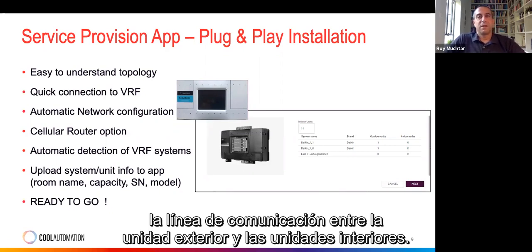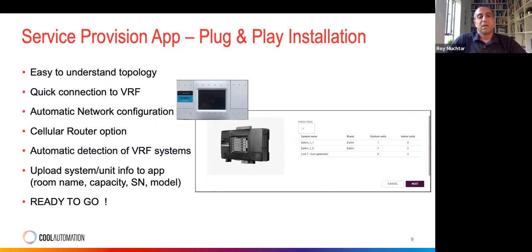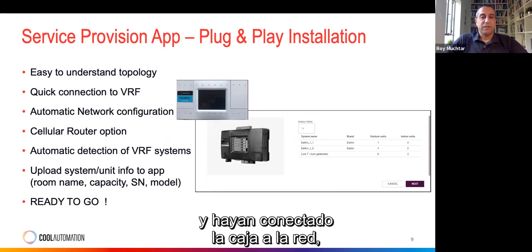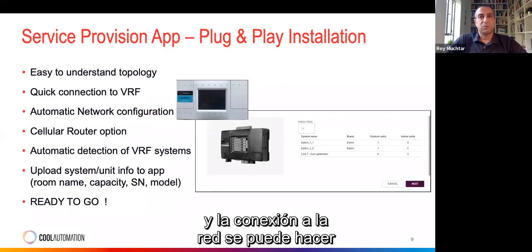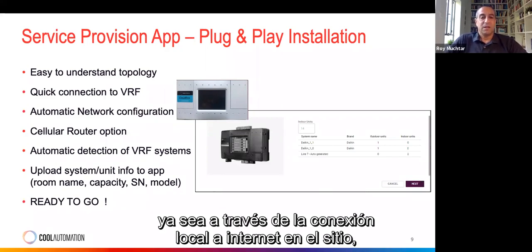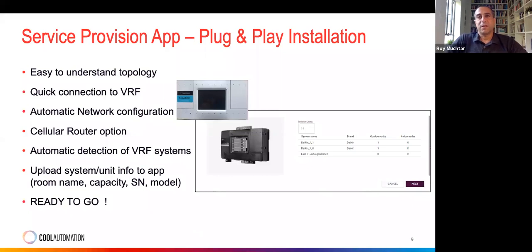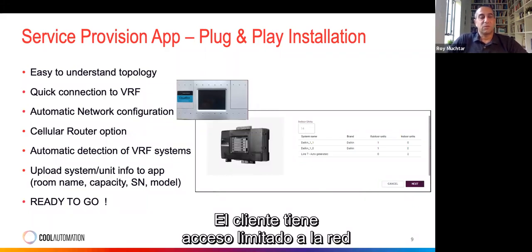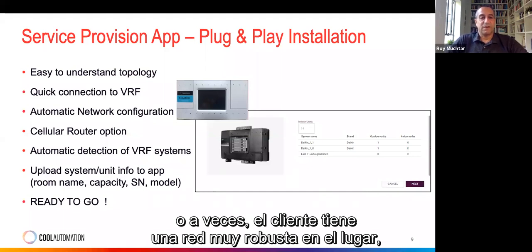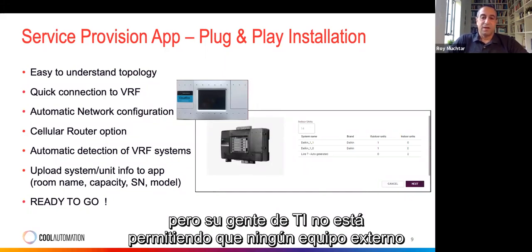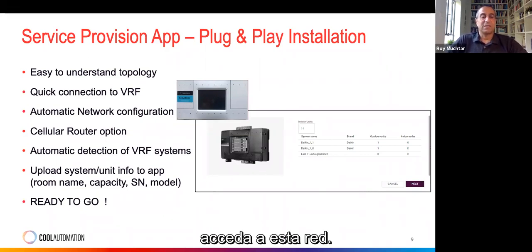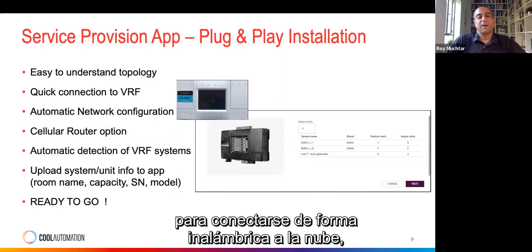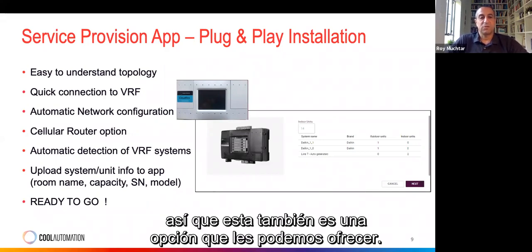The communication line between the outdoor unit and the indoor units, once connected, can be linked to the network either via a local Ethernet connection on site, or in places where the customer has limited network access, or a robust network whose IT team won't allow external equipment, you can use a cellular router to connect wirelessly to the cloud. This is also an option available from us.